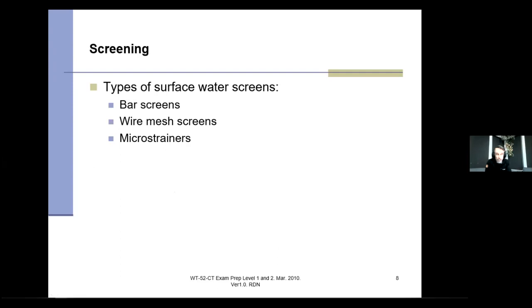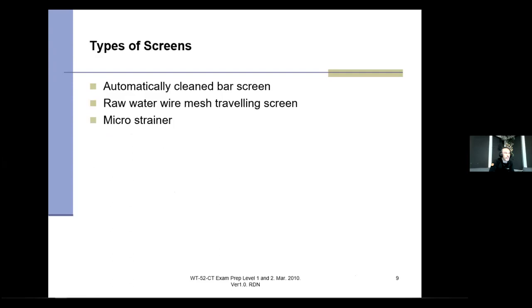We have a big giant one like that. And once a year, I actually hire a diver to go down and inspect and clean those intakes to make sure that they're doing their job. Again, they're made out of metal, right? Or some sort of stainless steel usually, and they should be inspected and looked at just in case.